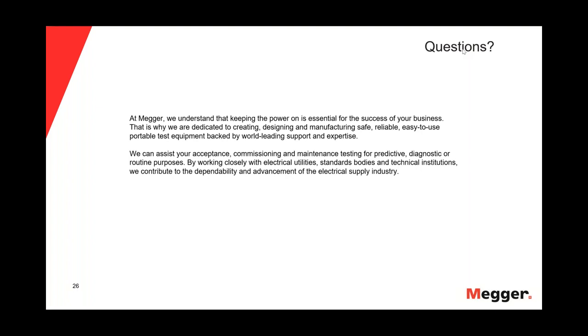Henning, which is the best method of cable testing, VLF or DAC tests? Okay. Which is superior? So let me make a basic statement. There are no good and no bad tests. There are different types of tests that are available, and any test method that is commercially available today has been proven to be a good test method. The real question is, what are you trying to do by testing a cable? What do you want to learn about a cable? And in that regard, the VLF and the DAC tell you different things.